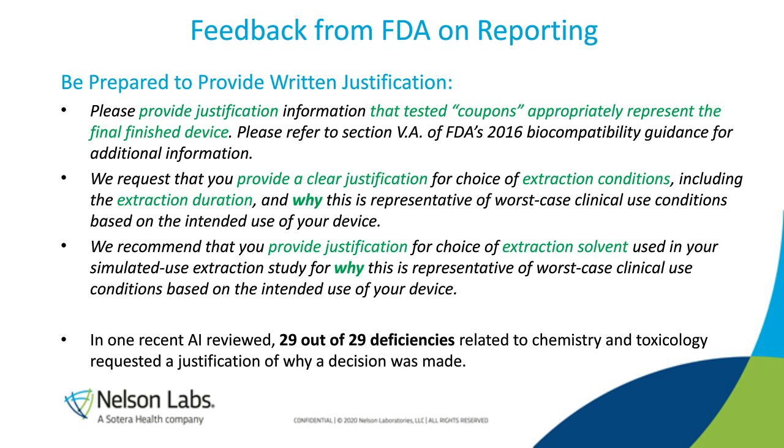They want an explanation why that's representative of worst case clinical use conditions. So now it's more than just following some sort of protocol. You really need to start scientifically defending this in writing in the report that gets in front of the FDA. And the same goes for the next bullet.